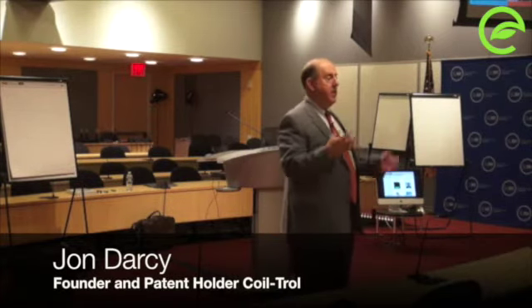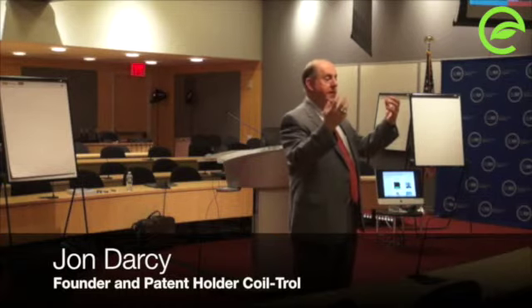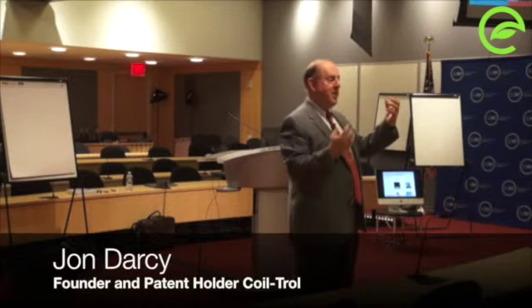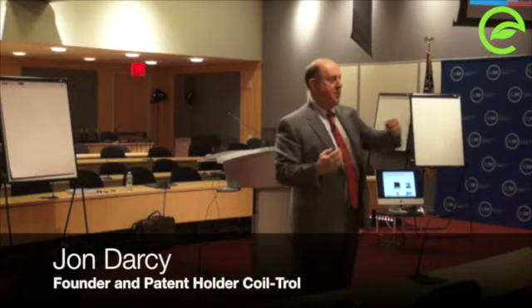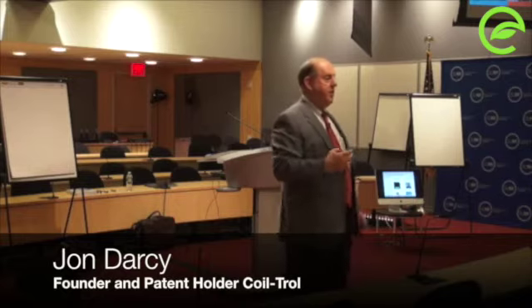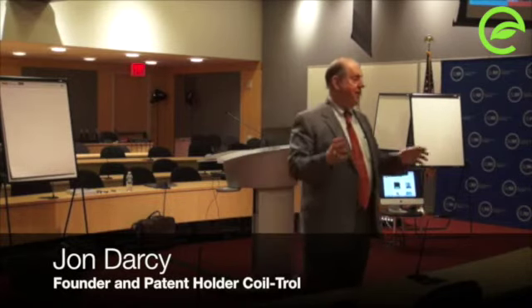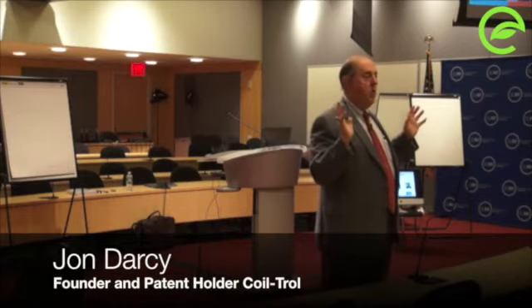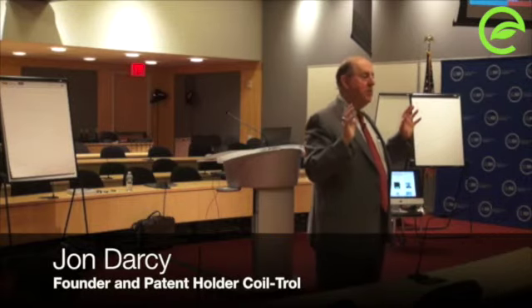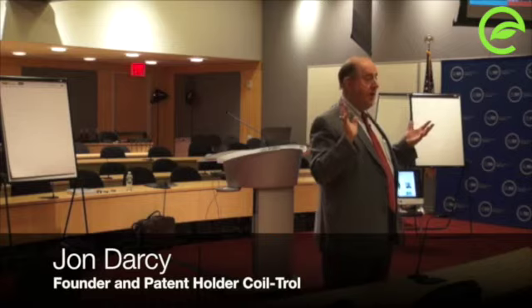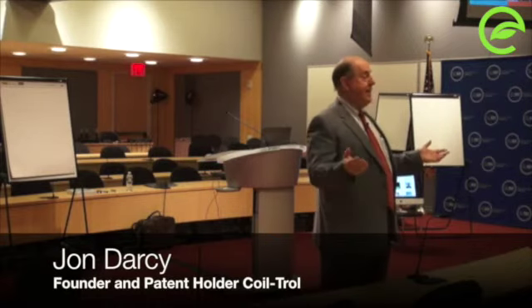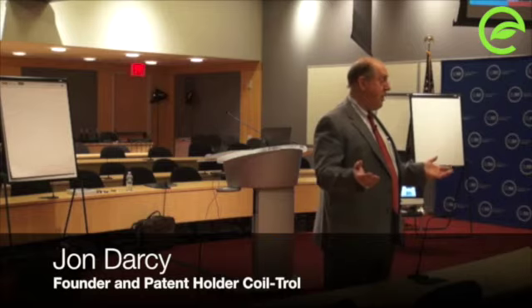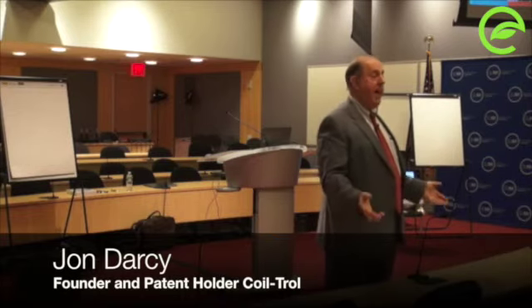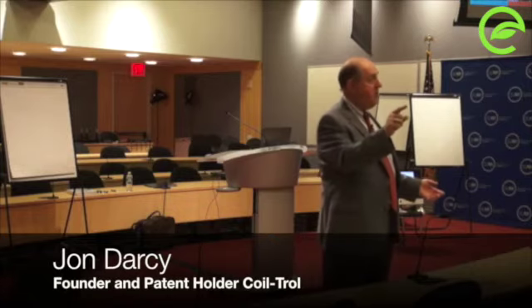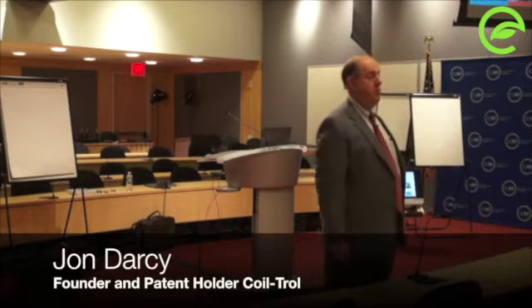You can't beat it. All you can beat it with is more energy. Let's keep cranking more humidity out. The faster you crank humidity out, the faster it comes in. So you're shoveling against the tide, right? You can't beat it. So all you want to do is pull your building down to 53 or 54%, or even better, grains. If you pull it down to 64 grains, then stop. Don't try to pull it down any further because you're wasting your time. And you're not going to lose your load. As long as that grain doesn't go above 64, you're not going to lose your load. It's not going to happen.